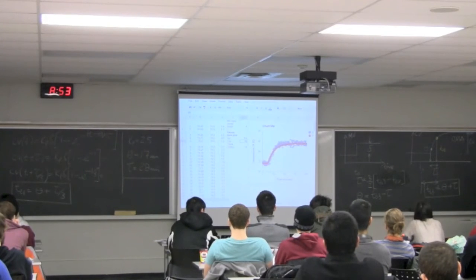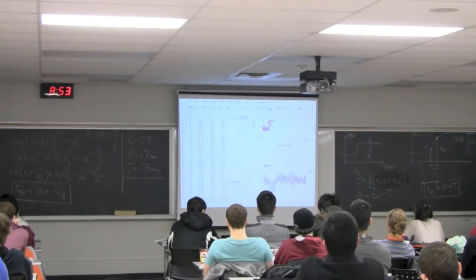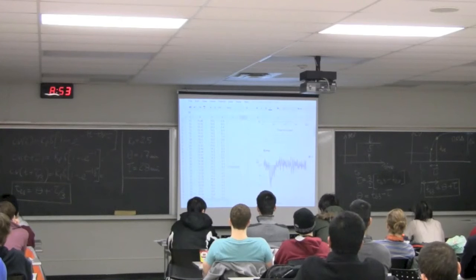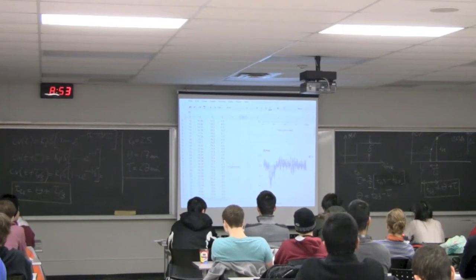The first two columns, that's the time data. I use this as equally spaced points in time. So one minute, two minutes, and so forth. The temperature, these were the data you measured from the process. Your thermocouple is on the process and you go to your computer database afterwards and get those first two columns. That's easy to get. The next column is the predicted temperature. What that is, is simply, I've used this equation. You may see it up here or down here. Sub this equation into Excel. That equation, then, is exactly KP times delta, 1 minus e to the minus t minus theta over tau. Sub in your values that you estimated using this method we showed on Friday. And if that red curve matches the blue curve to good accuracy, you're set. Then you know that you've done a reasonable job.